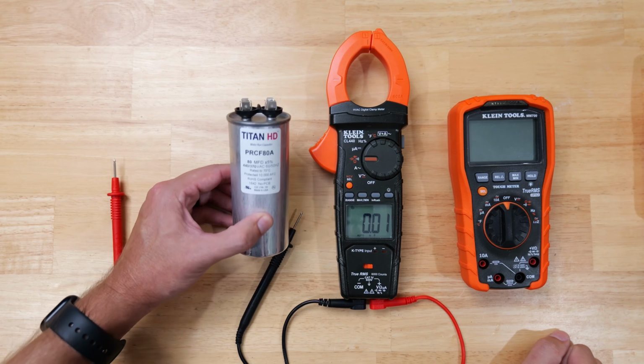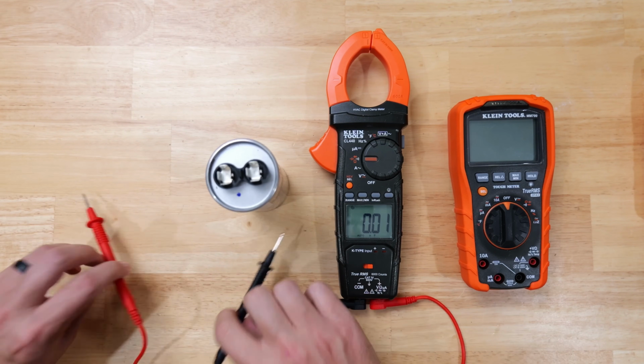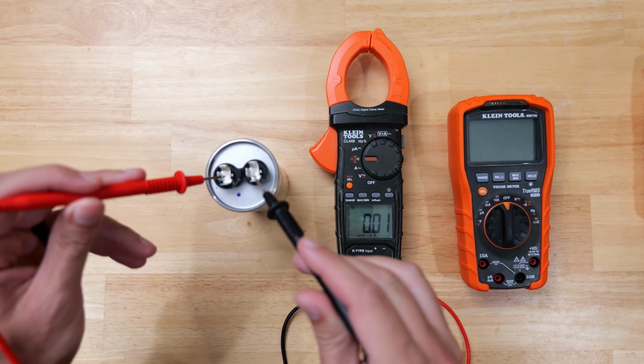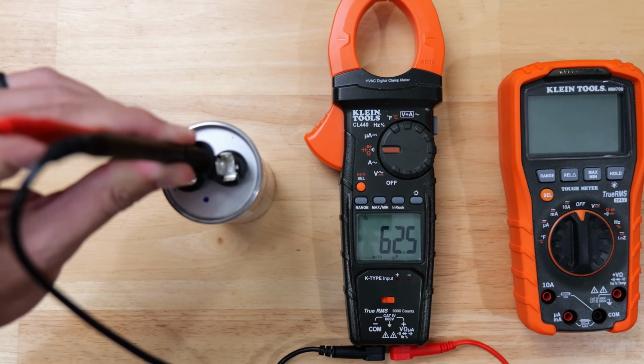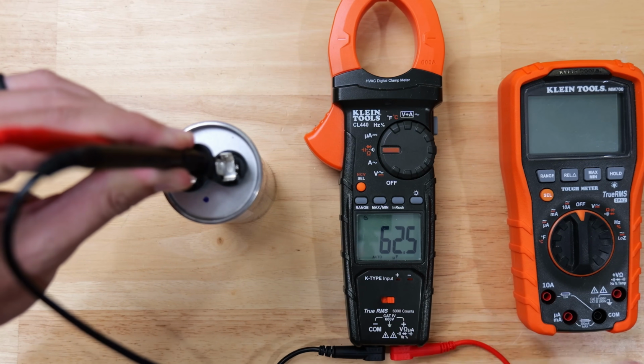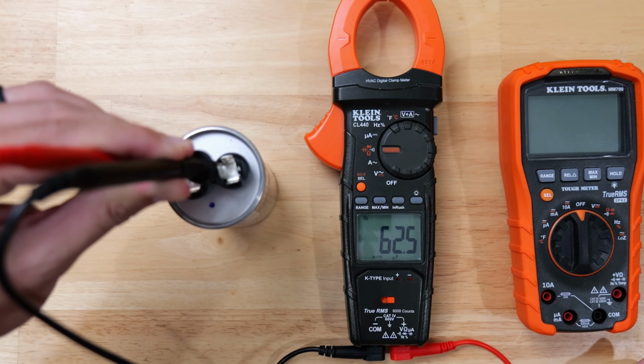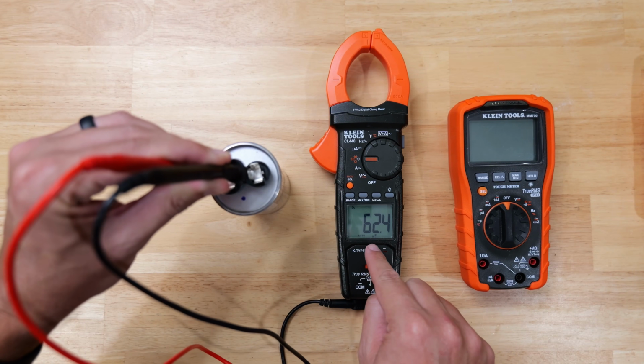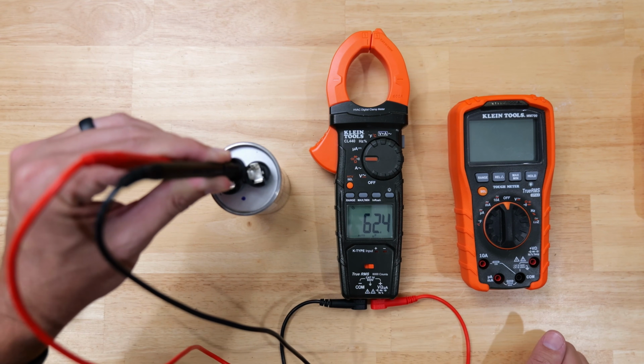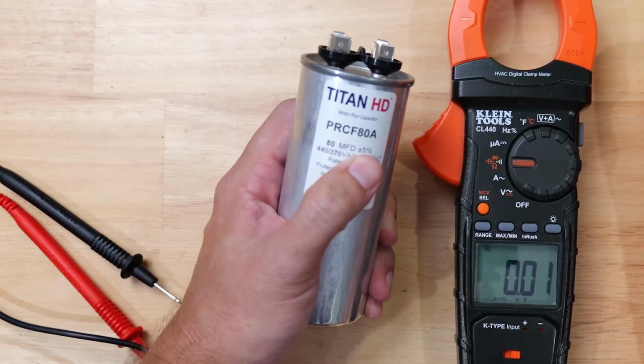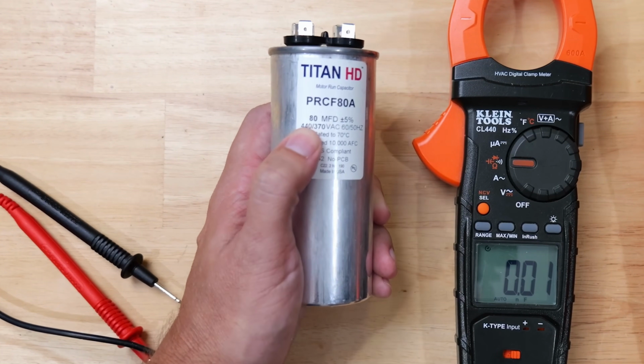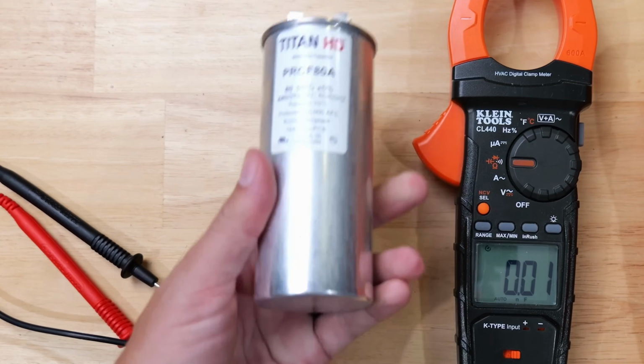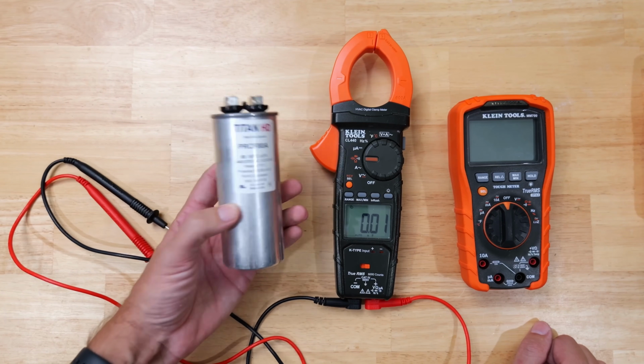With our standard motor run capacitor here, we just have two terminals. All I need to do is touch one probe to each terminal. As you can see, it's reading 62.5 microfarads—you know it's microfarads when it shows a U and an F. That's well below the 5% tolerance of where it should be at 80 microfarads, so this capacitor is bad.